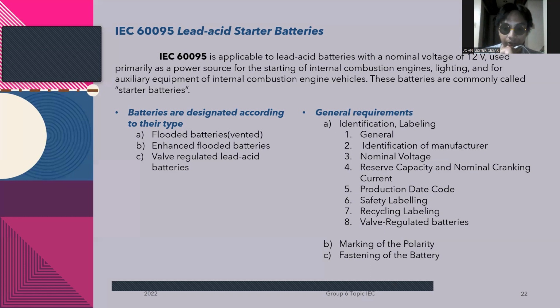Number 8. The valve-regulated batteries. Valve-regulated batteries shall be marked using the term VRLA. In addition, it is recommended that VRLA batteries shall bear special indication that the battery shall not be opened. Next, letter B is the marking of the polarity. The terminal shall be identified according to the requirements of IEC 60095-2 or of IEC 60095 Part 4.